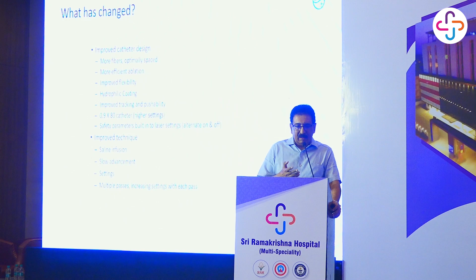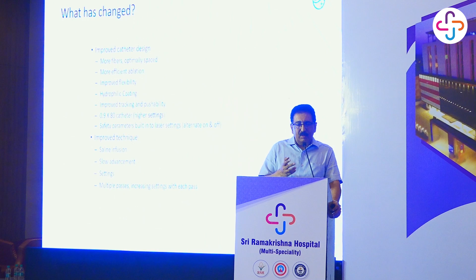So what has changed in the new laser? Because there are more fibers and more efficient ablation, the catheter has become more flexible, there is a hydrophilic coating now, and trackability and pushability have improved. Also, in the 0.9 mm catheter, up to 80 pulses can be given. Another new thing is that we infuse saline rather than contrast, because this helps to safely ablate the tissue with each pass. So what are the situations where this laser can be used? Some of the situations are when somebody has already had a stent and comes back with in-stent restenosis. This is one setting where laser is useful.